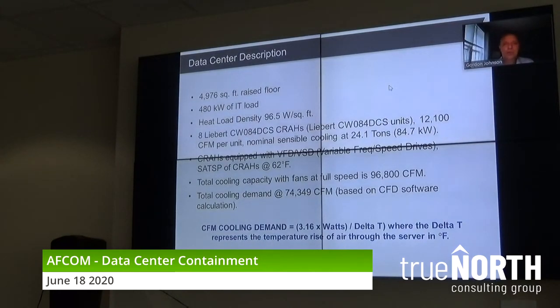We've got 8 CRAH units. A CRAH unit versus a CRAC, instead of a computer room air conditioner, is a computer room air handler. A CRAH has chilled water coming into it, and they always have variable frequency or speed drives where I can reduce the airflow to match the IT heat load. Although CRAC units are now being designed that enable you to do the same thing. The CRAH units, all 8, are going to be running at a maximum CFM, like that fourth bullet point, 12,100 CFM. I'm running at a very cold 62 degrees, so I'm not energy efficient, and I'll show you why.